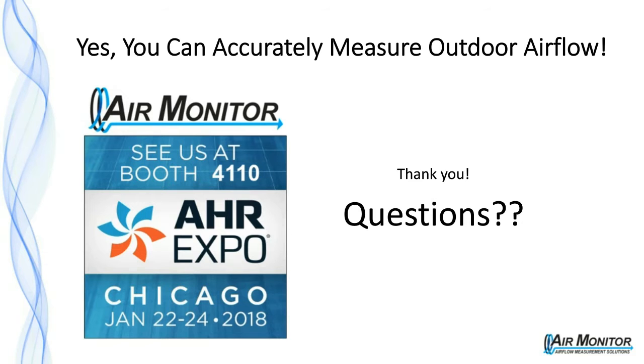Okay, another question that came in is, please explain turn down ratio again. This is Barry, and turn down ratio is, as simply put as possible, the maximum achievable flow rate of the instrument divided by the minimum, more or less, achievable flow rate of the instrument. Most instruments have an accuracy based on a certain flow rate range, and that range works from a minimum all the way through a maximum flow rate. So in determining the turn down, the first step is what's the maximum flow rate, divide that by the minimum set point, and you have the overall operating turn down of the device.